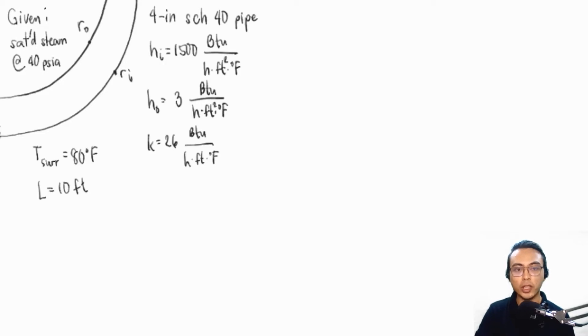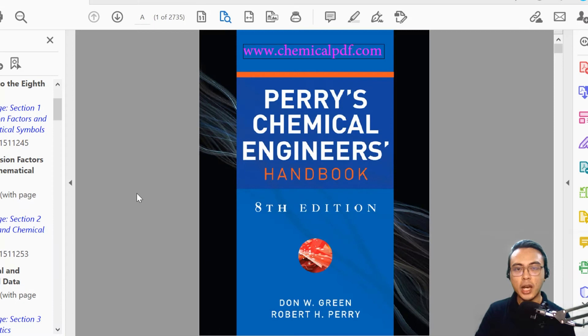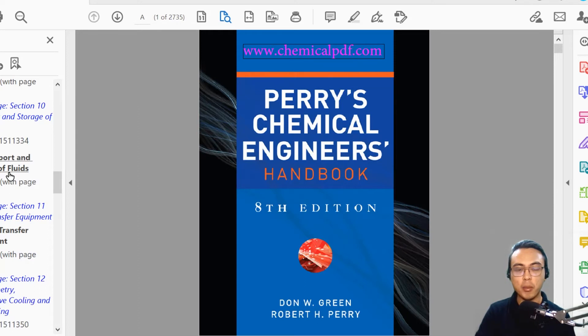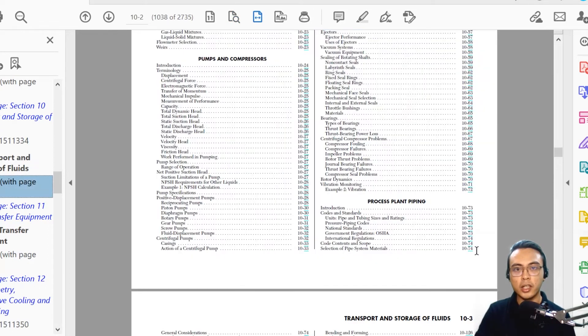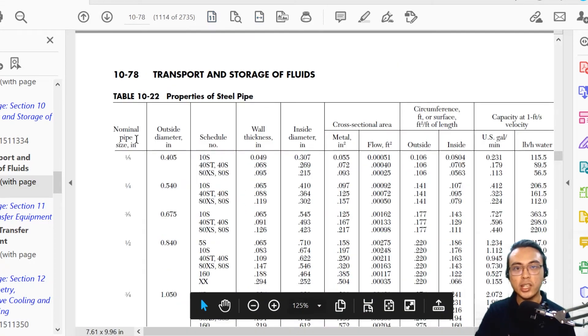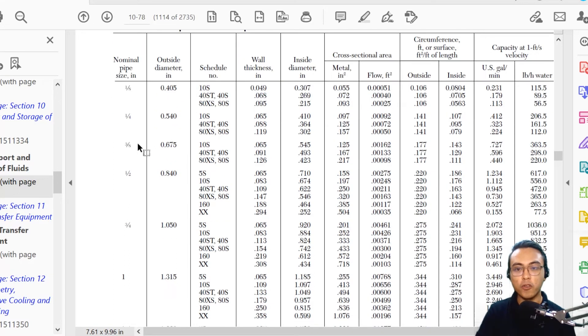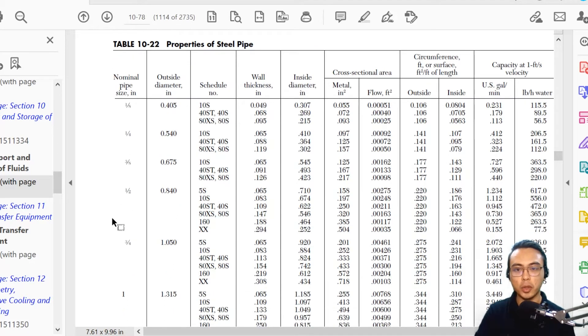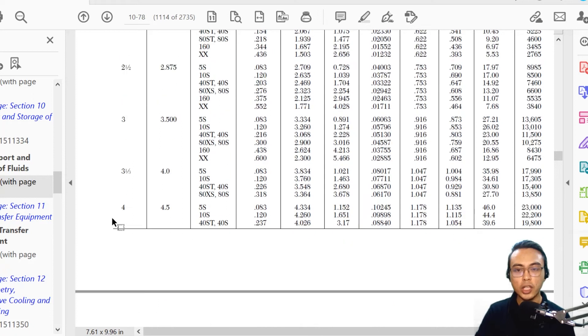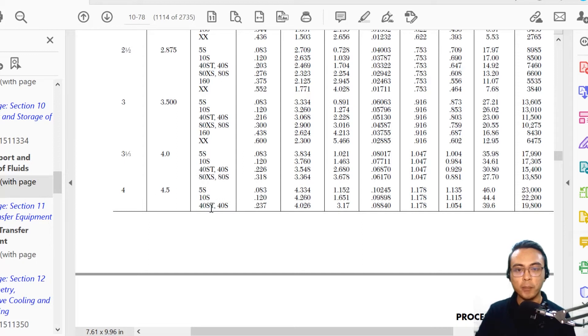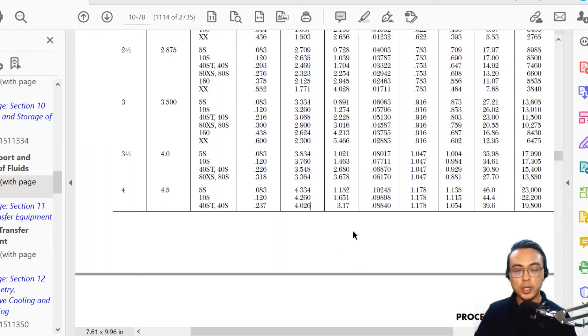Before we proceed, let's determine the actual internal diameter of the pipe. Our given is 4-inch Schedule 40 pipe. The 4 inches is the nominal diameter, not the actual diameter. For the actual diameter, we have to look at our handbook. The actual diameters are given in Chapter 10 of Perry's Chemical Engineers Handbook, 8th Edition, under Process Plants Piping. Looking at Table 10-22 for 4-inch Schedule 40, the outer diameter is 4.5 inches and the inside diameter is 4.026 inches.